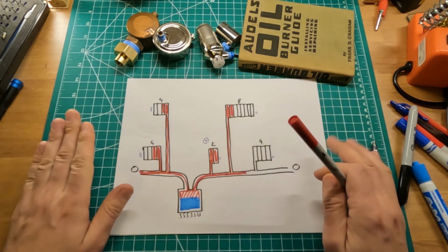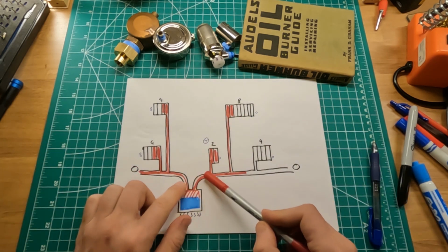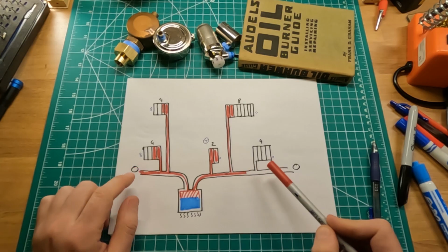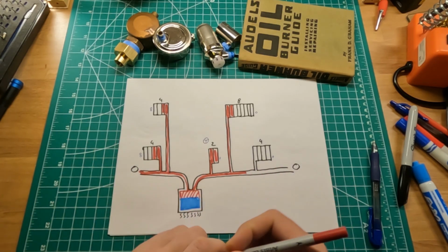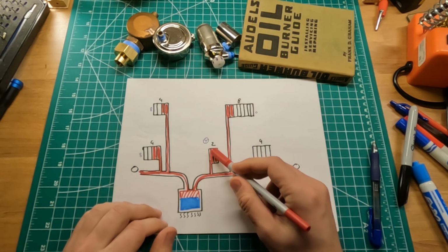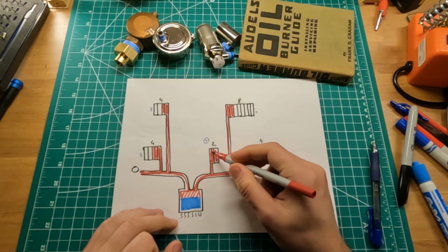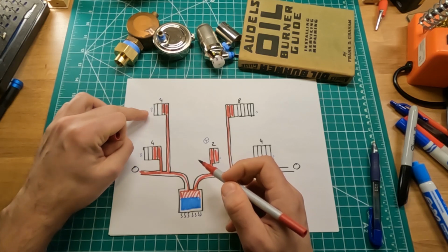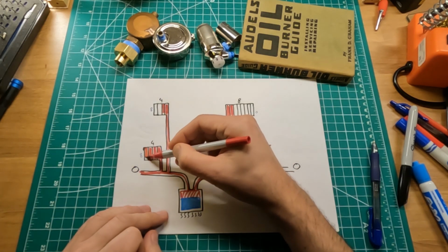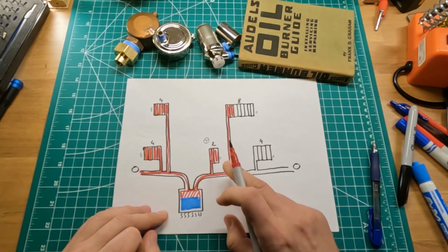So again, starting from scratch, the boiler keeps on producing heat. The mains get the heat up. Then this radiator fills up with heat, and in the process, because those 2 air vents have much bigger openings, those 2 radiators fill up with heat at the exact same time as this one.